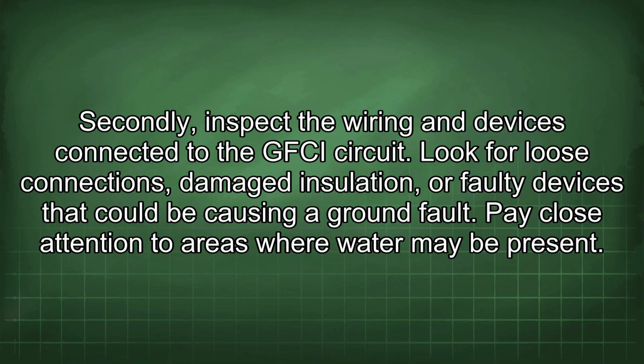Secondly, inspect the wiring and devices connected to the GFCI circuit. Look for loose connections, damaged insulation, or faulty devices that could be causing a ground fault. Pay close attention to areas where water may be present.